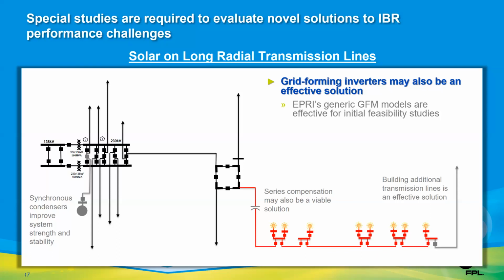One of the main takeaways that I want you to get from this slide is that we have conventional solutions in which we modify the grid to accommodate IBR, but we also need to keep pushing the envelope with the inverters themselves. And we need to provide feedback to our vendors on the capabilities that we're going to need going forward in order to avoid some of these expensive transmission level solutions for stability only issues. Next slide, please.